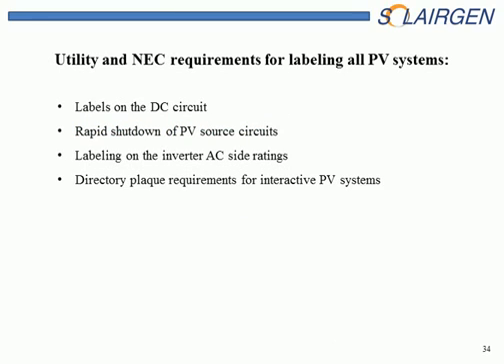Both the utility and the NEC have requirements for labeling PV systems. The National Electrical Code is enforced by local jurisdiction, which may or may not know what to look for. The utility knows that they want a label and a disconnect, so they're going to be the final line. So let's take a look at the requirements from these two entities.